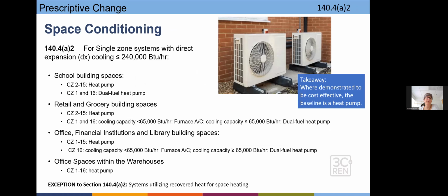For the space conditioning systems, what's significant is that wherever it's been shown to be cost effective, heat pumps are now the new baseline. This comes into play for single zone systems less than the 240,000 BTU/hour size, so that includes a lot of systems. It's then going to depend on the occupancy type and the climate zone, and that determines what you're allowed to do for that space.